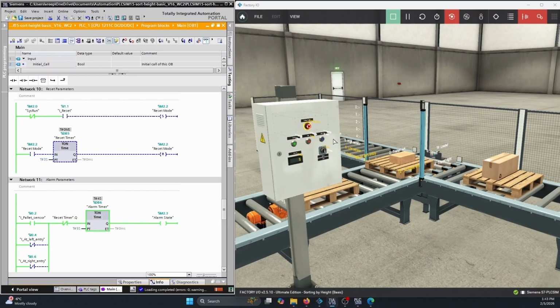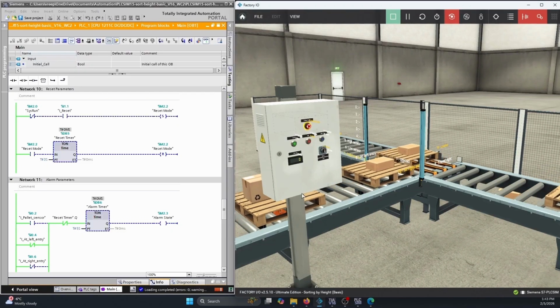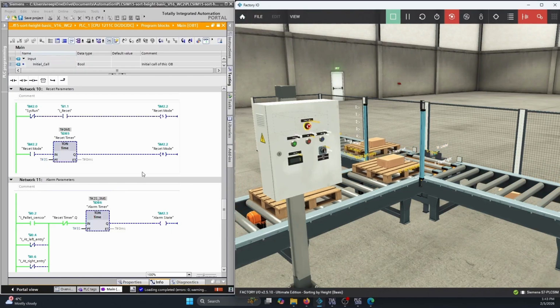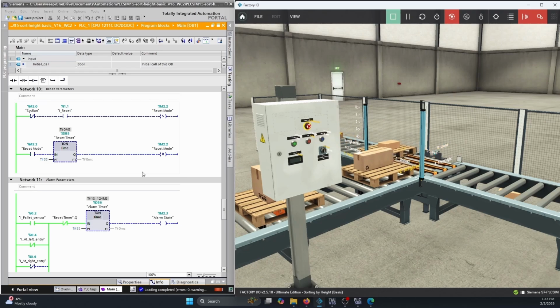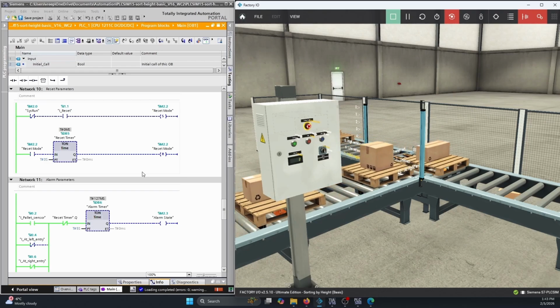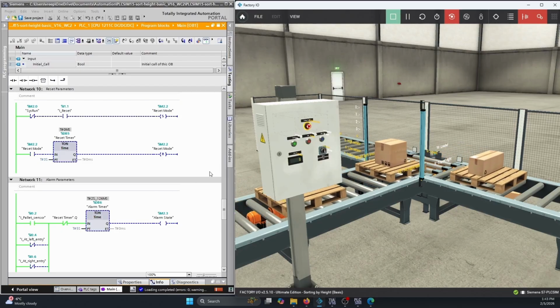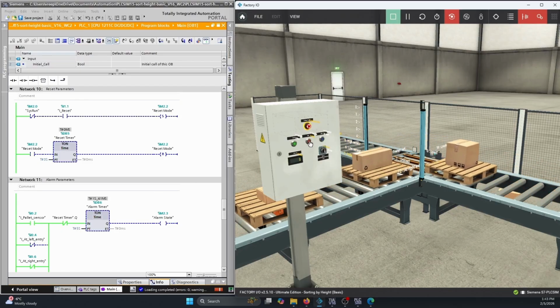Okay, so let's see whether we can reset. Let's reset our counter now. So we're pressing this for 3 seconds, resetting our counter. Our alarm state is out. We can start the unit up again, and now everything's rock and rolling. So let's just watch this for a couple seconds, see whether everything's working properly. Looks good. Getting nice counts. Everything seems to be working properly.